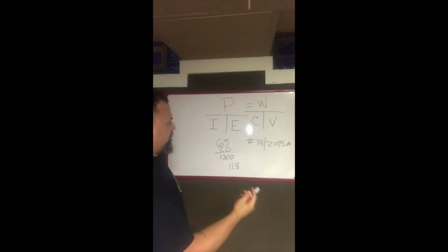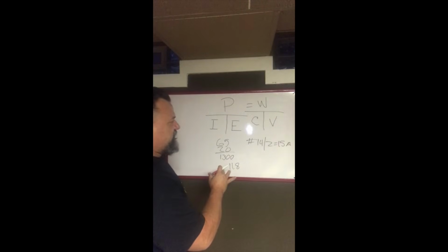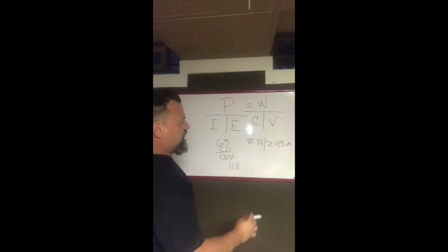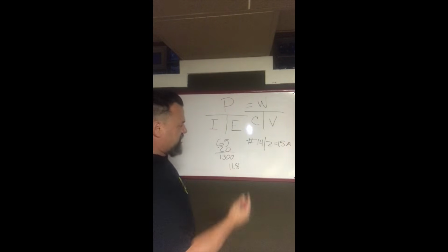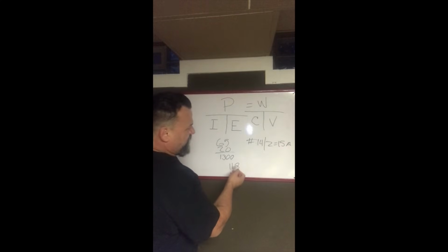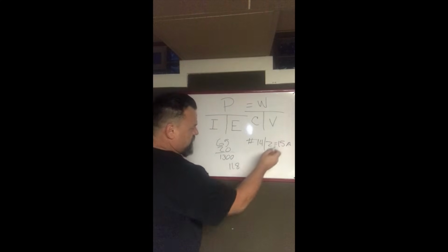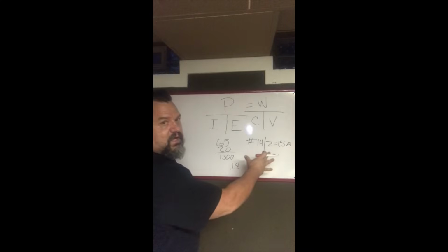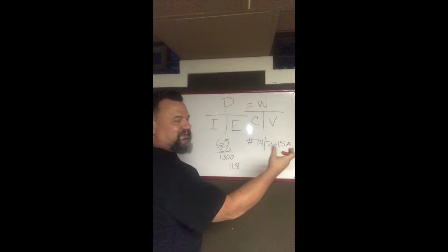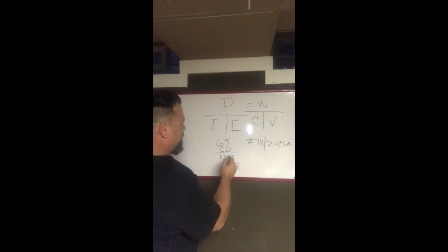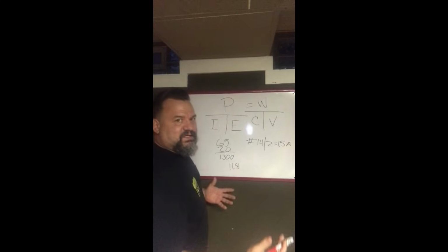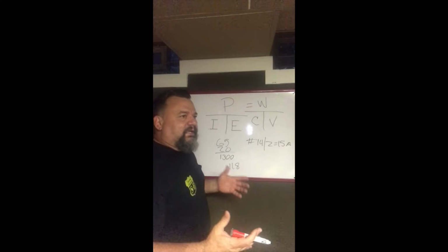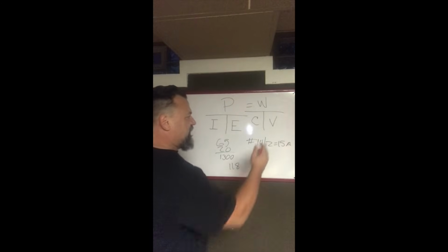Well, 11 amps is less than 15, so the minimum size that we would have inside of a house would be 14/2. So what would 11.8 amps be? The equivalent to 15 amps. You don't want to go to 15. You put anything else on that circuit, you're going to max it out, and it's going to pop. So I would put all 20 of those on one circuit at 11 amps. That seems safe to me. There's no motor. It's not going to spike or anything else like that.